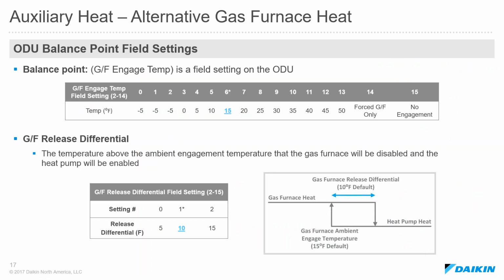So now we found out what balance point is. We found out that WebXpress calculates it for us. We looked at a few examples, and now we're going to look at how to actually apply it to the product. So there's a field setting on the outdoor unit. By default, it's 15 degrees. So if you do nothing, that A coil is going to lock itself out at 15 degrees and bring on the gas furnace. But it's configurable in 5-degree increments, as low as -5, as high as 50. And you can also force gas furnace only, or you can force no gas furnace at all. And that's, again, a field setting on the outdoor unit. It's 2-14, and you can find the same information in the installation manual or the service manual.